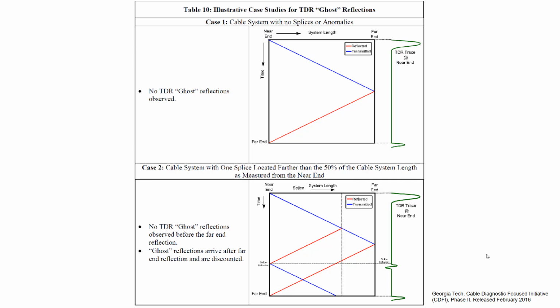Then the most important thing is to understand what happens when we conduct a test like this. You can see here clearly there are different cases which are studied. The first one is the simple case without any joints. Now this graph, most of you may have been introduced to, I think, when wave theory is introduced in power systems. But let me explain here again. So this is the cable. This is the near end and this is the far end. And this is the time scale.